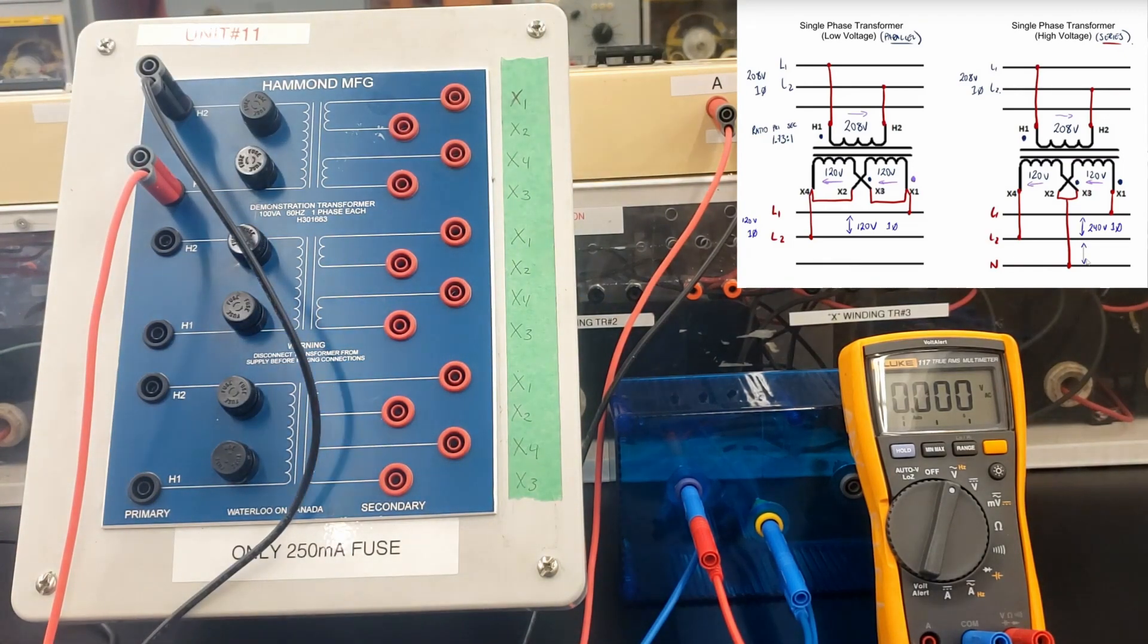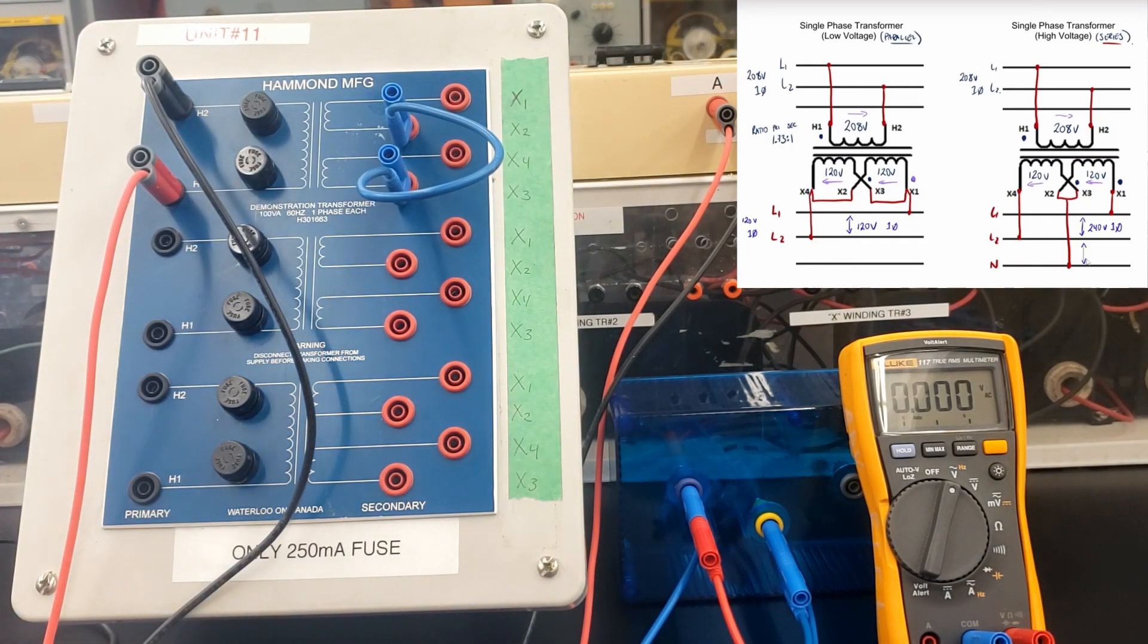Let's de-energize this guy. We're keeping the same primary voltage. H1 and H2 can remain the same. I'm going to take my connections off for these two guys right here. And then, I'm going to series up X2 and X3. We're on page 15 now. We're jumpering X2 and X3.